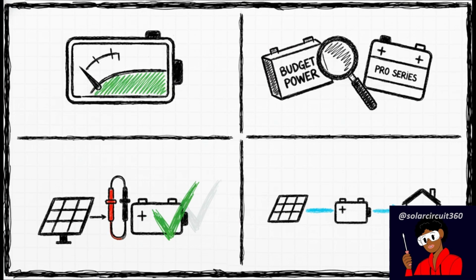It means when you're planning your power system, you should base your math on about 80 to 90% of the advertised capacity, not the full 100. It means you need to be extra skeptical of those super cheap, no-name brands, because they're usually the ones exaggerating the most. And at the end of the day, a real capacity test is the only way to know for sure what you've got, so you can size your whole system correctly.